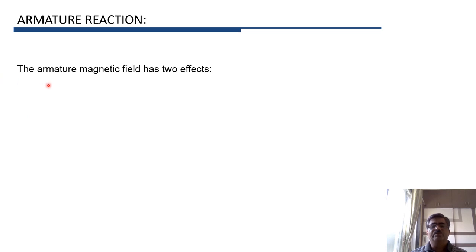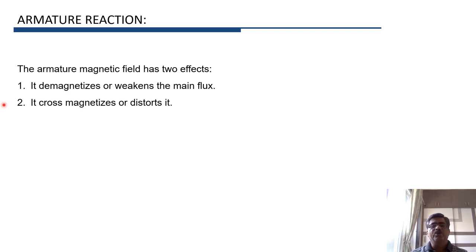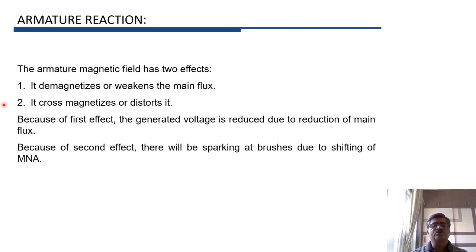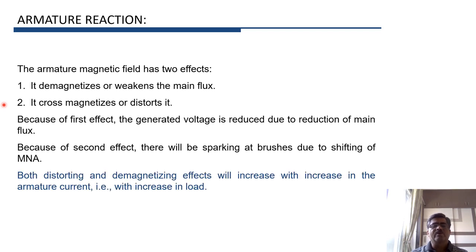In our previous videos we studied the effects of armature reaction. Because of armature reaction there is demagnetization or weakening of the main flux, and there is also cross-magnetization or distortion of the main flux. Because of the first effect the generated voltage is reduced, and because of the second effect commutation will not be proper — there will be sparking at brushes — mainly because of shifting of the magnetic neutral axis. Both these effects increase with increase in armature current, that is with increase in load.